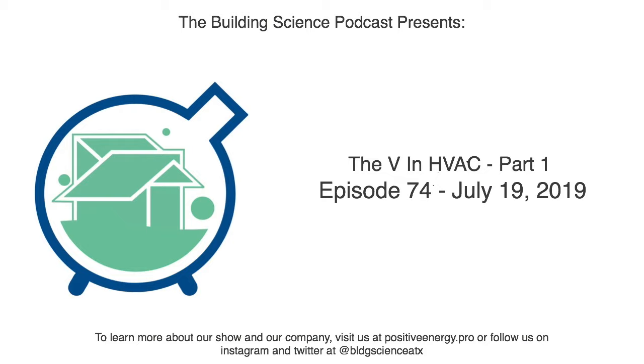If you have a 90% sensible recovery effectiveness, then using this system you're able to recover 90% of the heat from the outdoor airstream and transfer that to the indoor. 90% of the delta of the temperature difference. That's amazing. Does it translate down to 18 degrees? 90% of 20? Exactly. So if that's our example and we have a 20 degree delta T and a 90% sensible recovery effectiveness, then we're going to be moving 18 degrees.